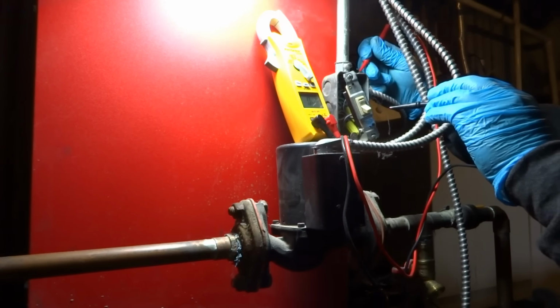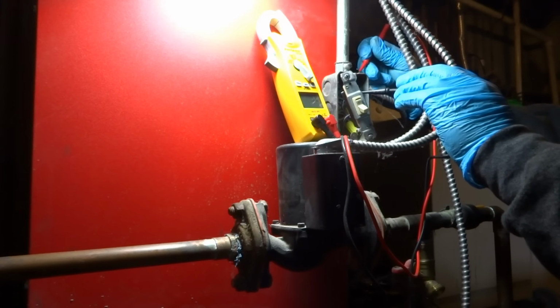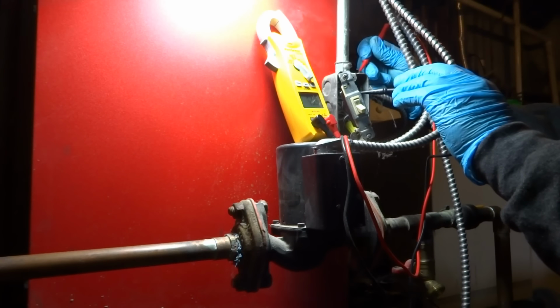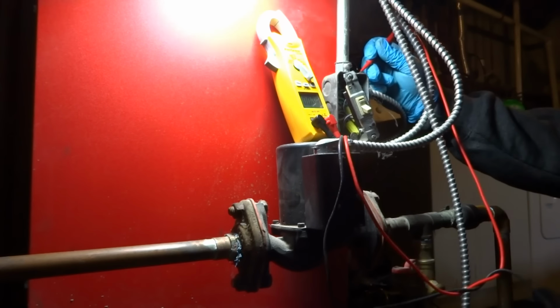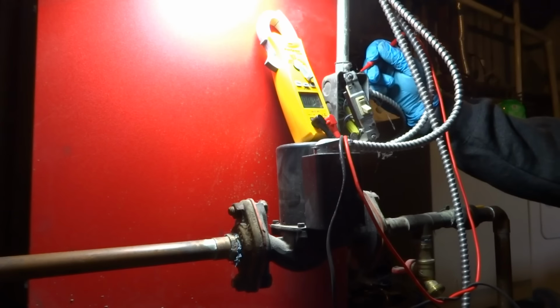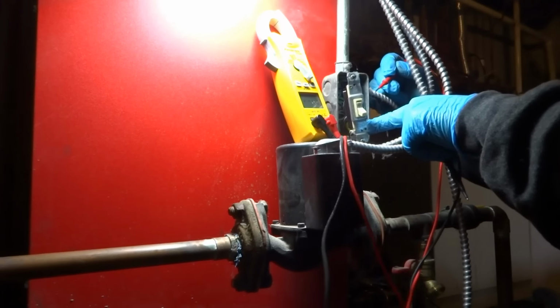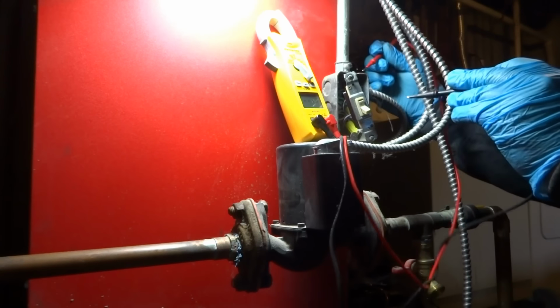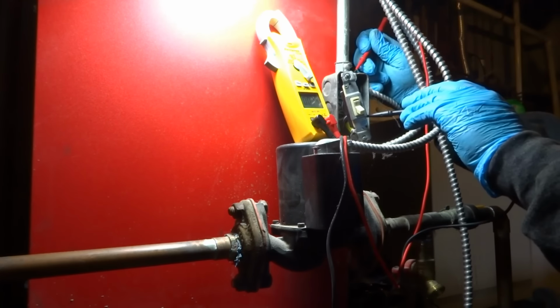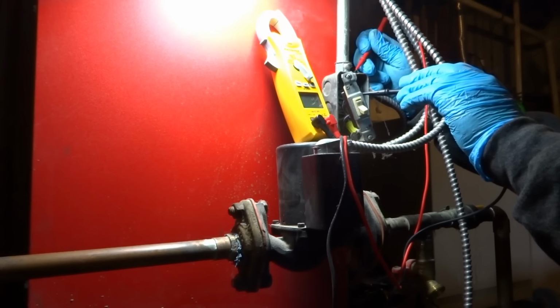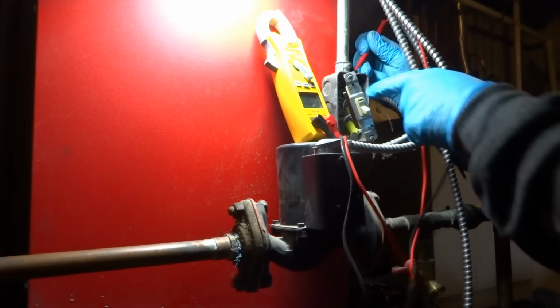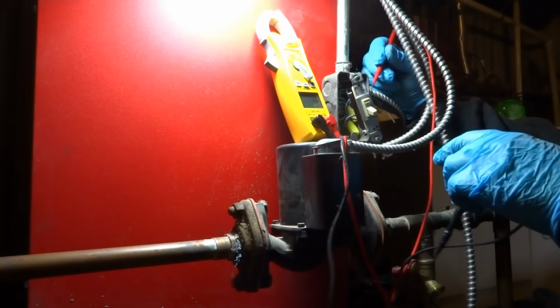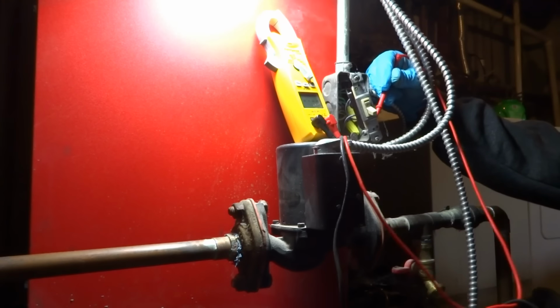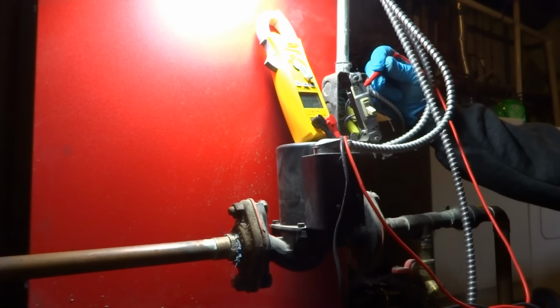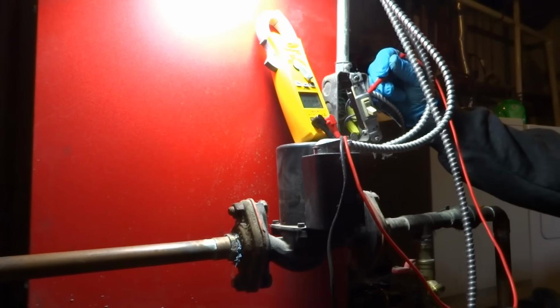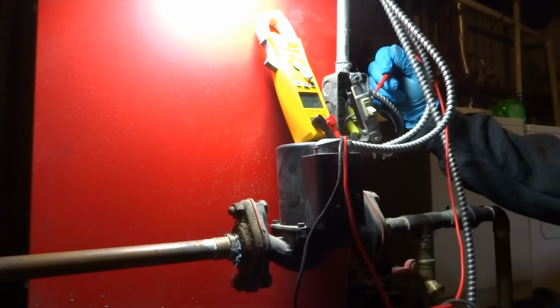That's the line going to the circulators, so that means you've got power going up there. That's the line going to the circulators that we've got an issue with. The line comes in and it's off, unless it's this breaker—no, because this is off. So that line right there feeds in, power comes in, and then it goes to the circulators and to that burner over there. So it's going to be the circulator circuit that's the problem.